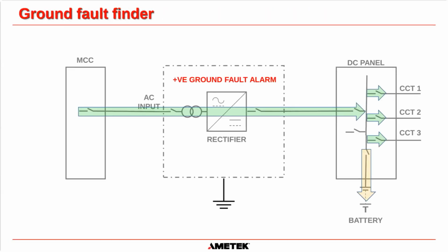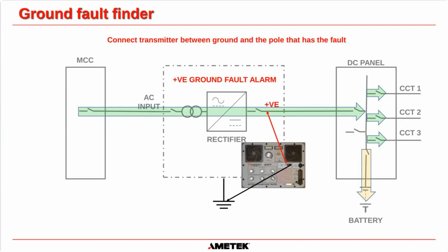So once again, we've got the positive ground fault alarm. And if you've got the Megger battery ground fault tracer, what you do is you have two leads that you need to connect to the system. And it doesn't really matter where you connect it in the system when you're connecting the signal probes. Basically, we know it's a positive ground fault, so we have to connect the red lead to the positive, and we have to connect the black lead to ground, okay?